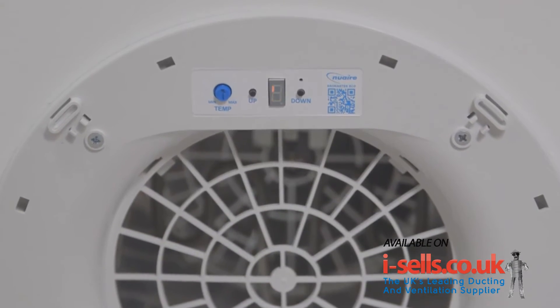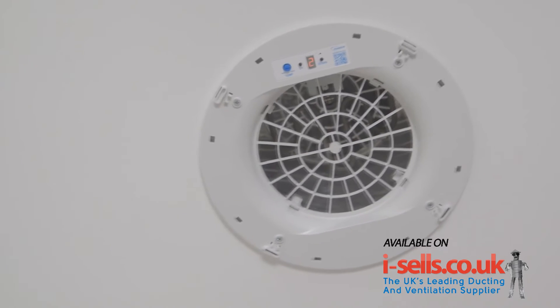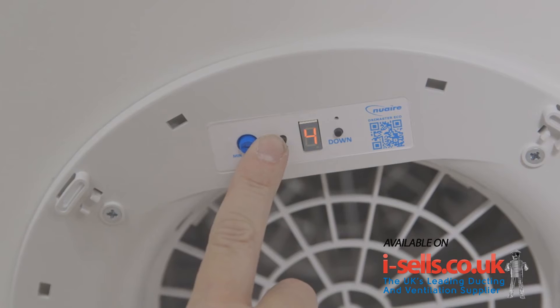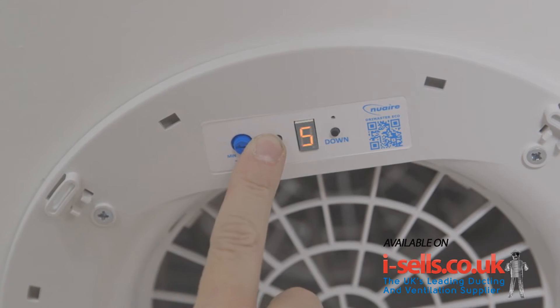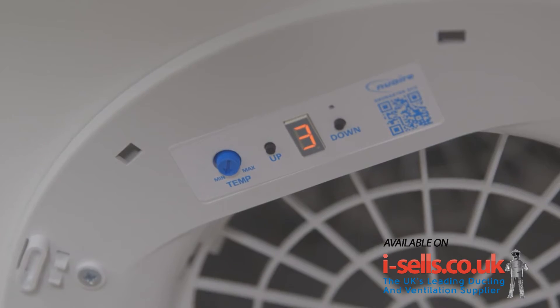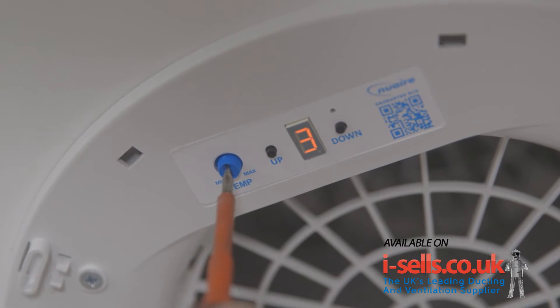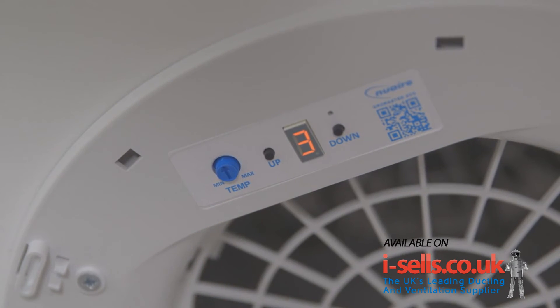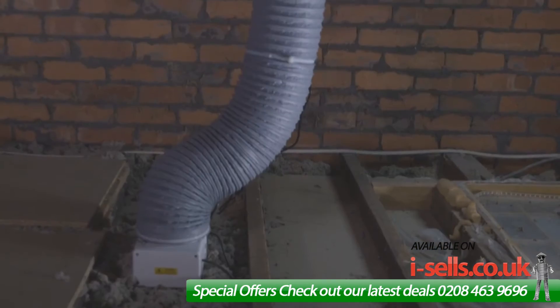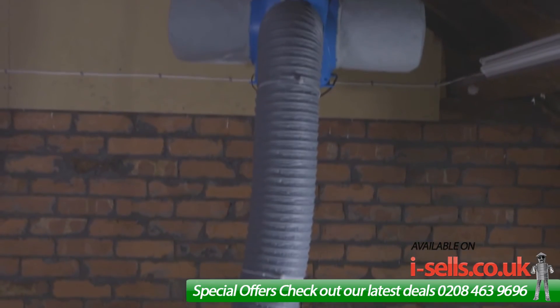Once powered up, the Drimaster Eco will automatically go through the temperature control option for 2 minutes. After the 2 minutes has elapsed, the unit will display the fan speed. To set the fan speed, press the up or down button. It's important when setting the heater temperature to turn the dial to set your target temperature — we recommend a midpoint of 10 degrees. When the supply air falls below this set point, the heater will automatically switch on, and when the supply air is above 10 degrees Celsius, it will automatically shut off to save energy for the user.